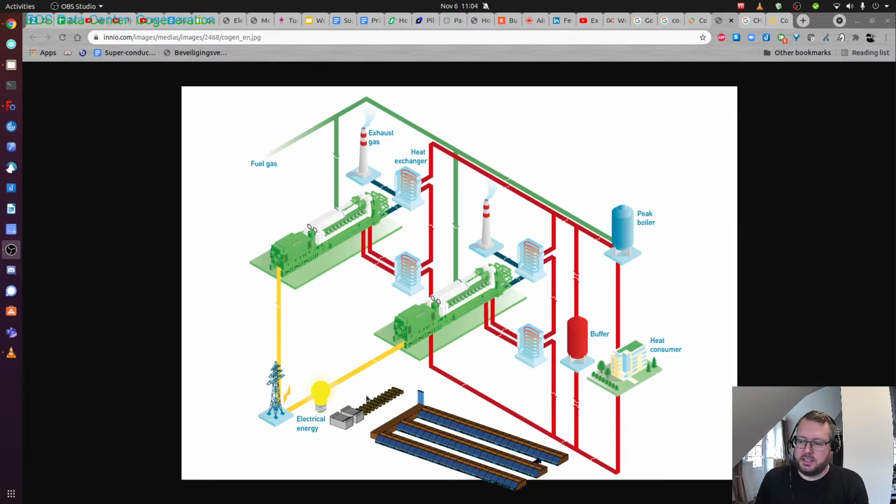And this is why cogeneration is so interesting, and it's just been enabled by recent developments in the ability to quick start gas gensets, making this not a huge capex for the data center operator. Maintenance, capex, fuel, running this for the grid is 100% paid by the utility. And only in the case of a grid failure, you have a power plant that you know works because it's not running 300 hours, but rather a minimum of 20% of the time to create flexible energy. And with that, you then have backup as a service and only pay for the hours that you actually have a failure.